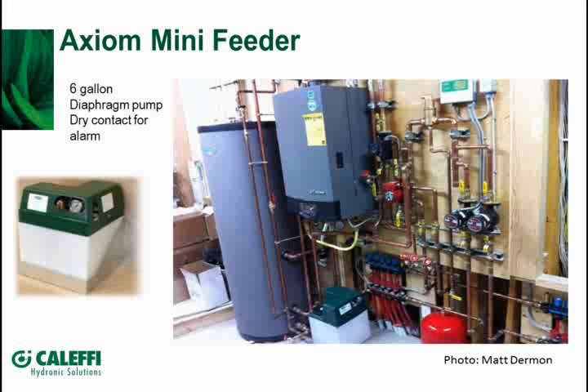Another nice system that you can put in is Axiom and some other brands of these out there. I think Xylem, the old Bell & Gossett company, makes a feeder similar to this. This is something that will hold a couple of gallons of your system fluid, your glycol, or whatever's going into it. It's got a gauge, a pressure regulator built into it, and a little electric pump in there. So you just fill the system up with your fluid, plug it in, and it'll maintain the system pressure. Another way of doing it, instead of using one of those expansion tanks like I showed earlier.